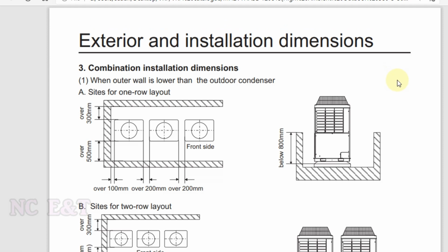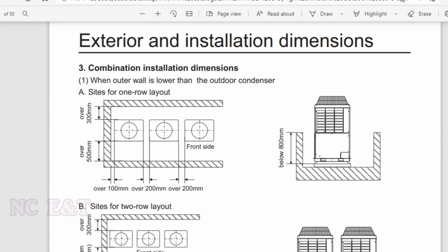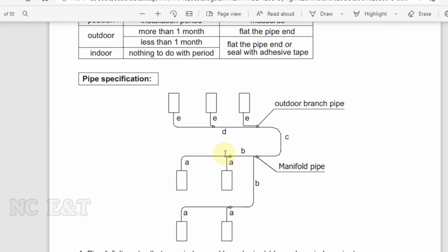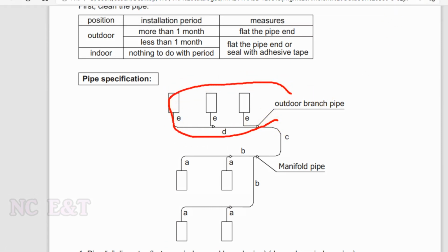This way we can design the VRF circuits, decide how many circuits we need, design the location of the outdoor units, and select the piping route. For designing the diameter of the pipe, there are different tables provided by the supplier. As per the capacity of the indoor unit, we can select the pipe diameter. We can look at an example of it. This picture is showing 3 outdoor units connected to 4 indoor units.